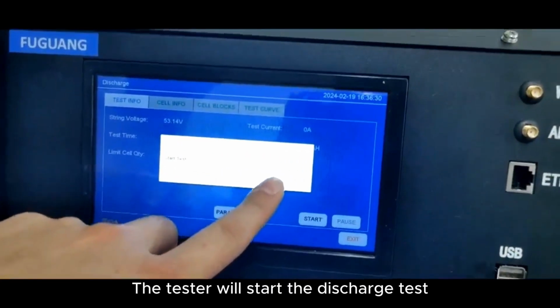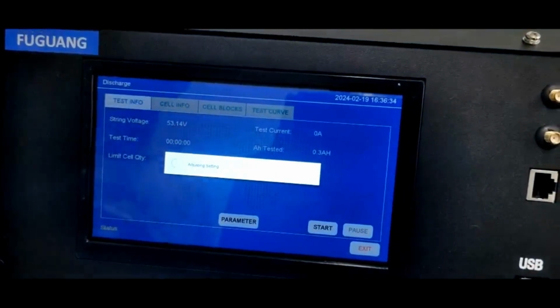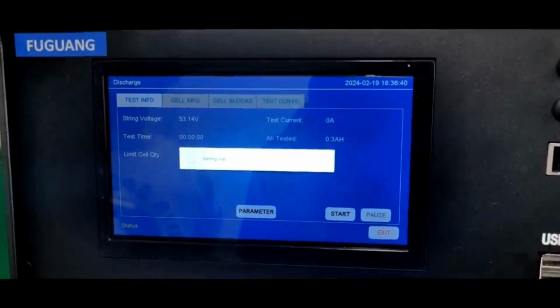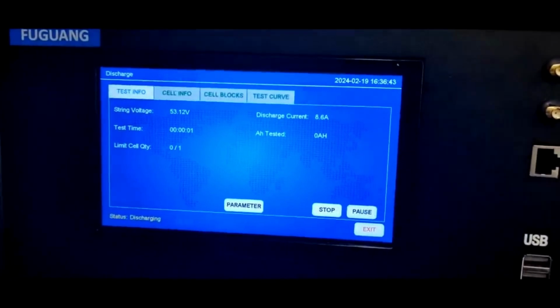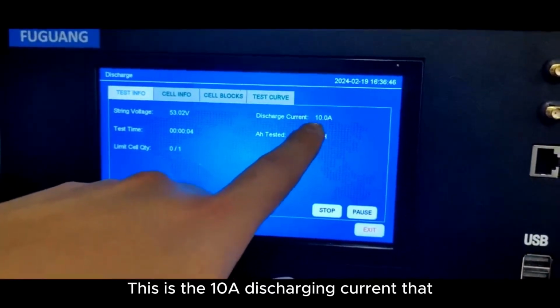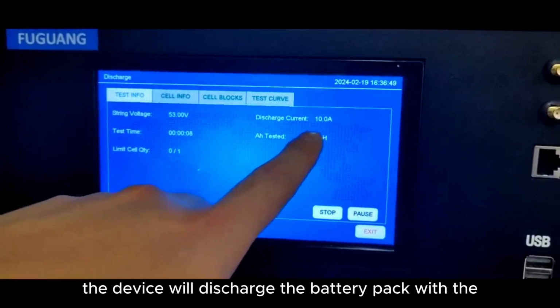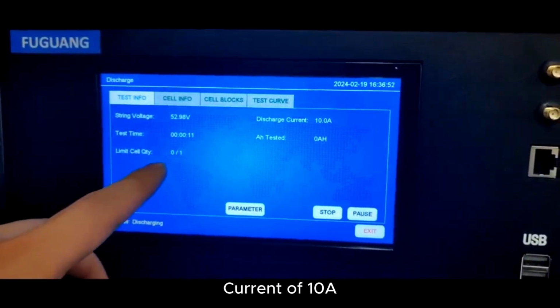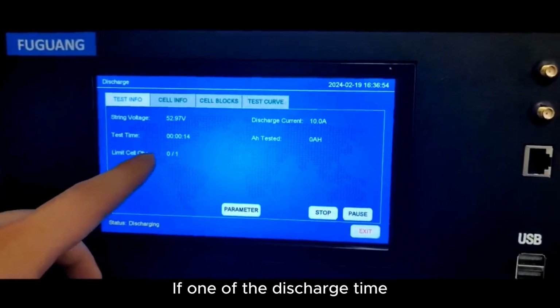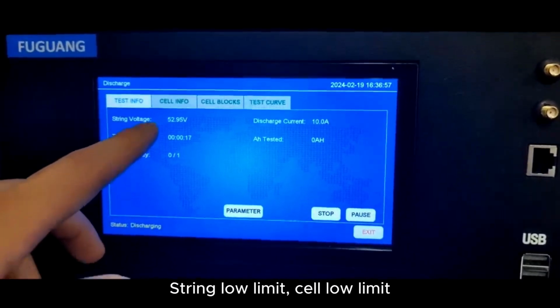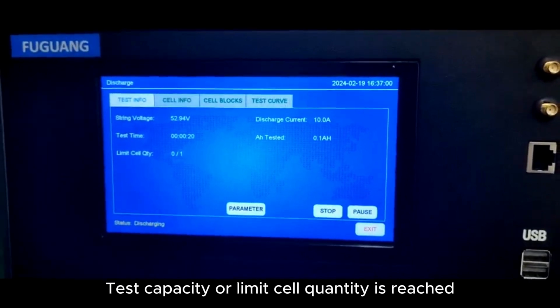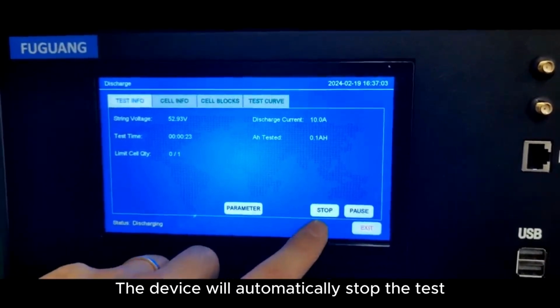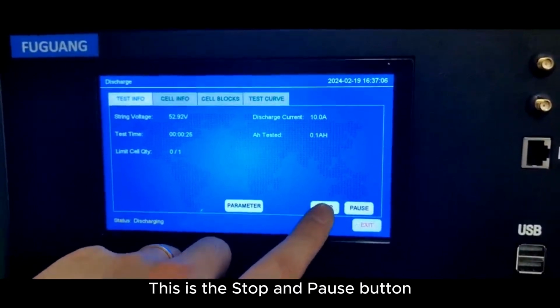Click Start on the discharge test page and confirm OK. The tester will start the discharge test. This is the 10 ampere discharging current that we just set in the parameter settings. The device will discharge the battery pack with the current of 10 ampere. If one of the discharge time, string low limit, cell low limit, test capacity, or limit cell quantity is reached, the device will automatically stop the test. This is the stop and pause button. Click Stop and the test automatically stops.